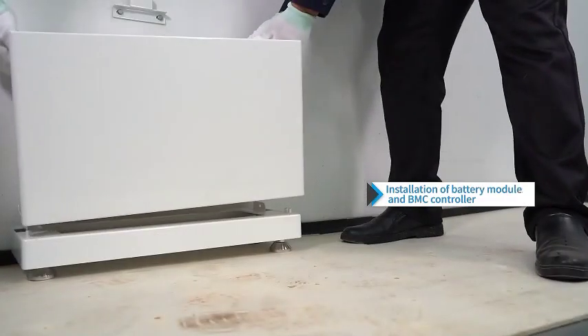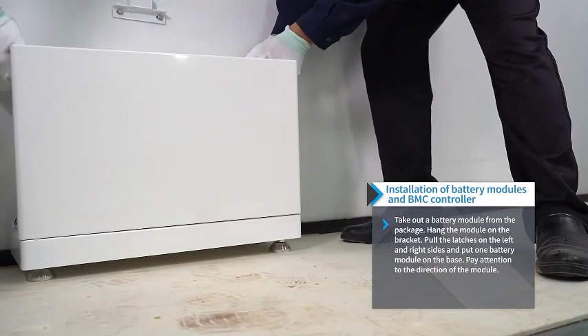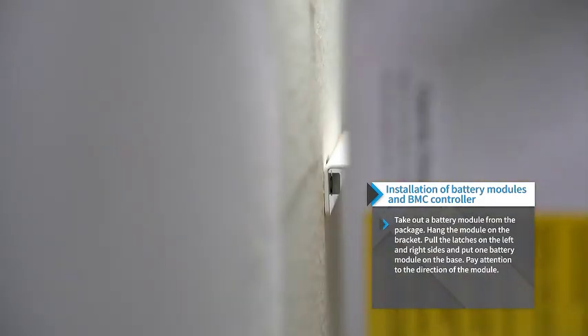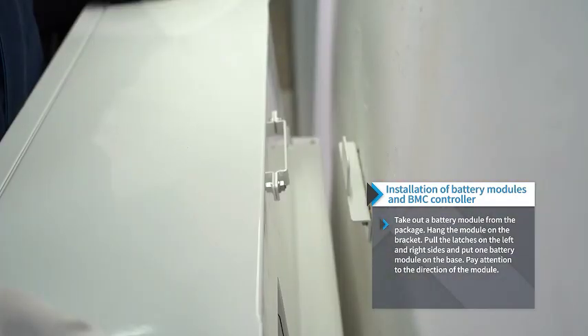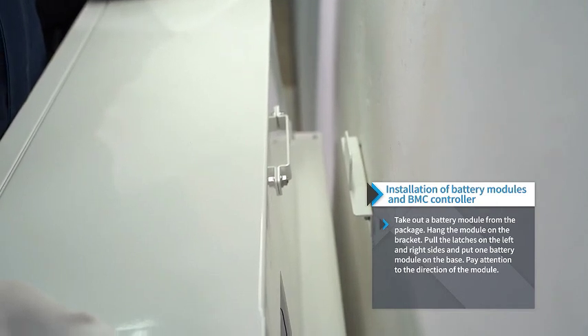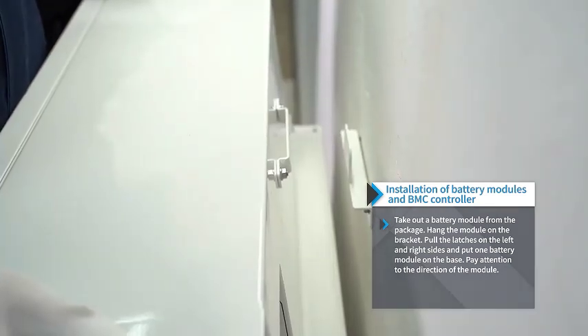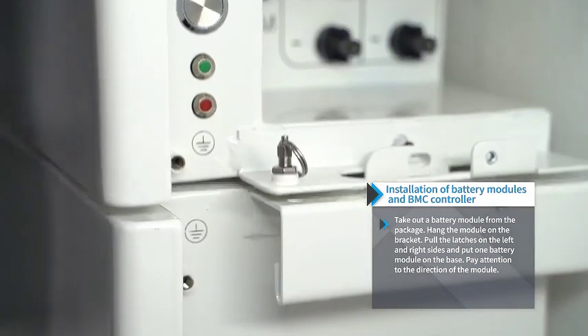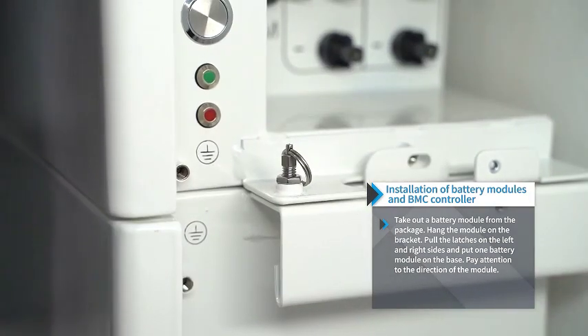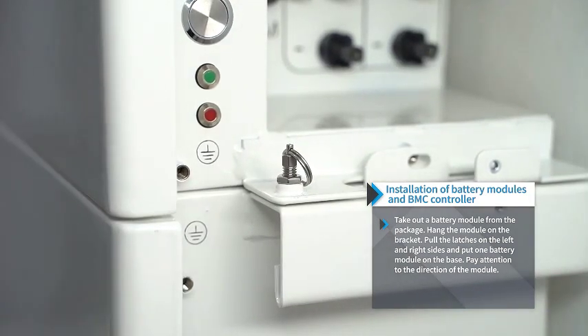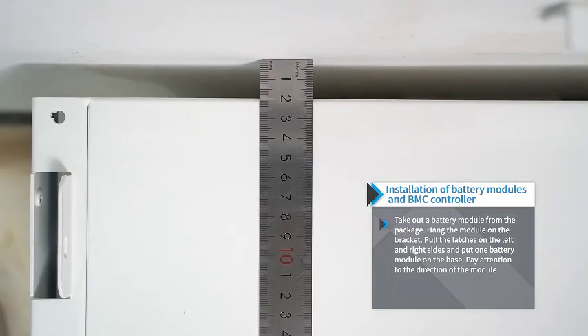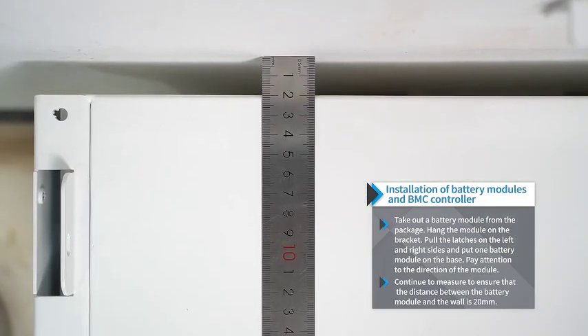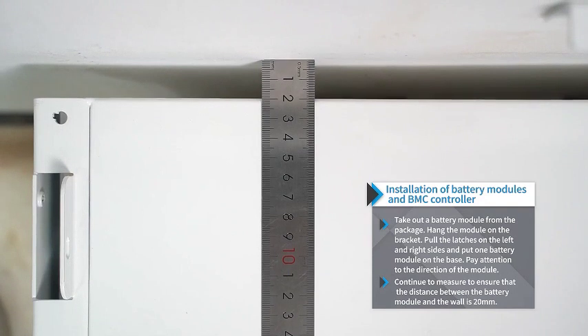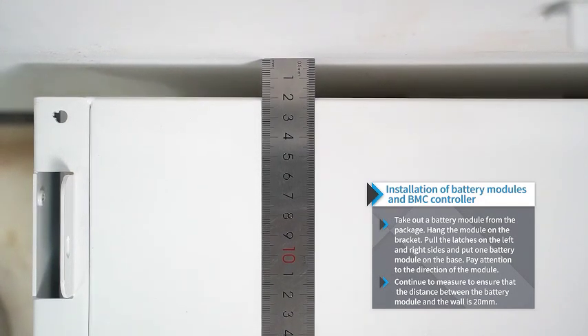Installation of battery modules and BMC controller. Take out the battery module from the package. Hang the battery module on the bracket. Pull the latches on the left and right sides and put one battery module on the base. Pay attention to the direction of the module. Continue to measure to ensure the distance between the battery module and the wall is 20 millimeters.